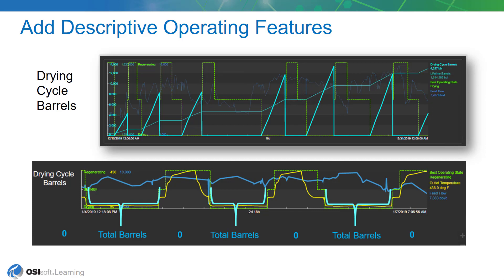Once we have the dryer states defined, we can calculate the other two descriptive operating features. The first one will be the drying cycle barrels — you can see a trend of that value in the PI Vision display as the light blue trace. It's a sawtooth trend where we're accumulating the barrels during drying cycles. It only adds to the total when the dryer is in drying mode, and then it resets to zero at the start of each regeneration cycle.